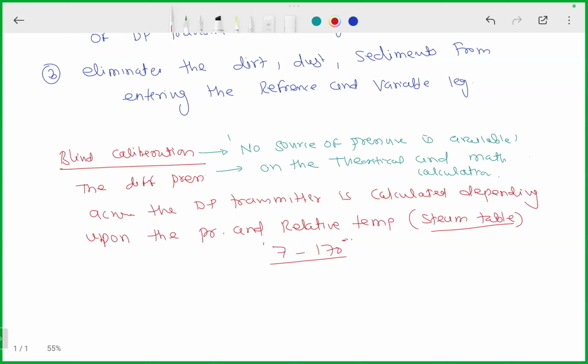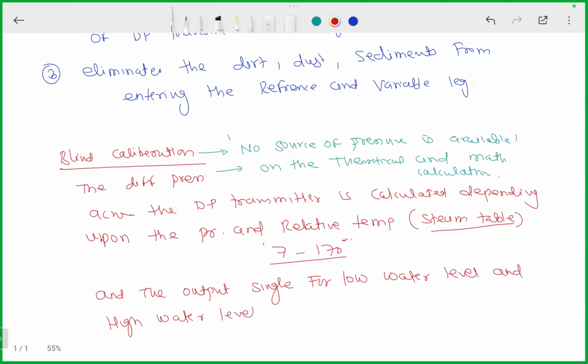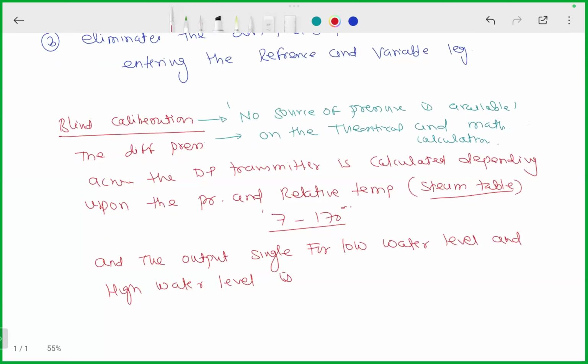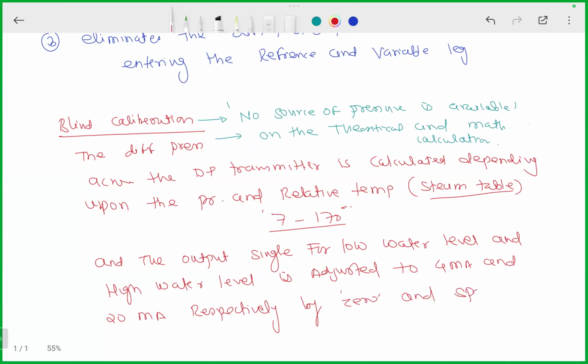Differential pressure across the DP transmitter is calculated depending upon the pressure and relative temperature, and the output signal for low water level and high water level is adjusted to 4 milliamp and 20 milliamp respectively by zero and span setting.